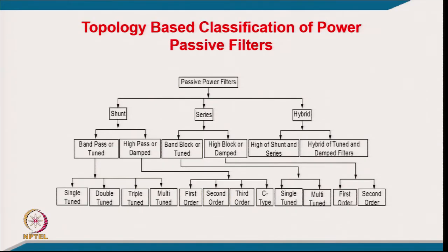But you can understand that for all higher order harmonics the power associated is not too much, but certainly for an electronic circuit or communication network, even a small power can cause a reasonable disturbance or interference to the system. So, certainly we have to suppress all these higher order harmonics locally. For the tuned filter we have a choice whether we want to use 1, 2, 3 or how many, but certainly the damp filter or high pass filter is mandatory along with the tuned filter.